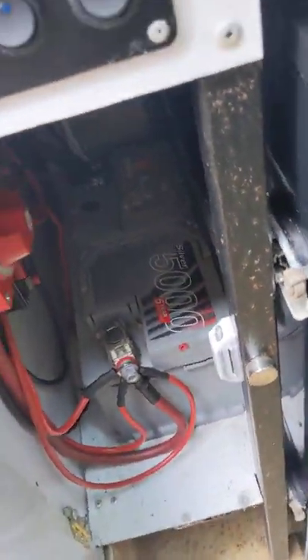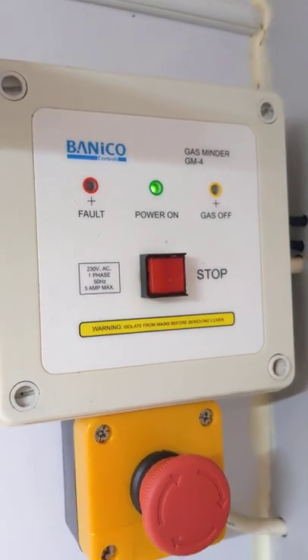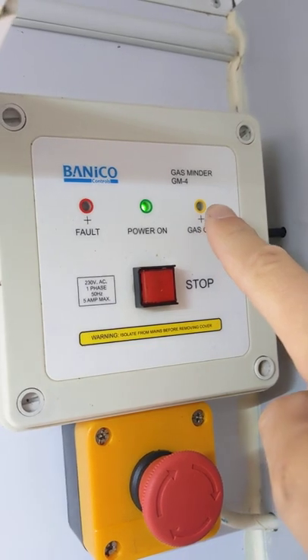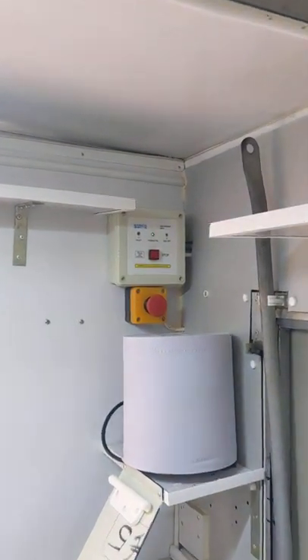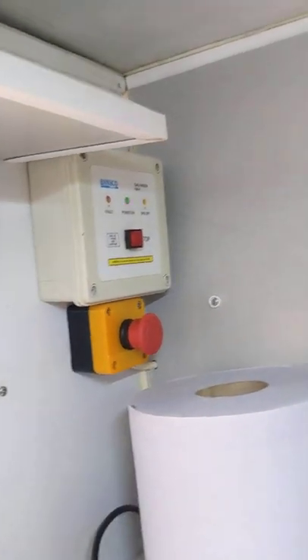The safety mechanism I mentioned — where you need the roof and door open — runs on 240V. Our printer and POS system also ran on 240V. Down here we have an inverter: if I turn that on you'll see two plugs. One is for the gas cutoff system — you can see it says 'power on' up there. If I close the roof, the 'gas off' light would illuminate, cutting the gas. There's also a stop button you can hit on the way out if there's a fire or anything goes wrong.